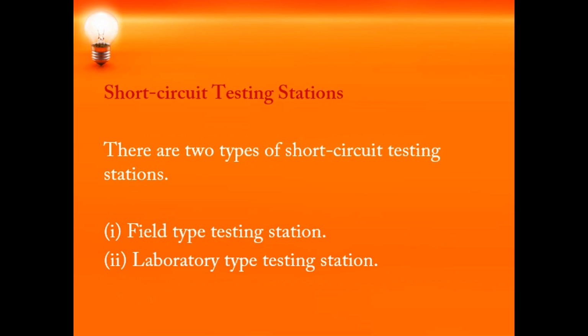So first we will move on to short circuit testing stations. Okay, mainly there are two types of short circuit testing stations. One is in the field, that is under the existing real situations, the present situation, and the other one is the laboratory type, where you have a setup. So short circuit testing will be performed either on the field or on the laboratory type testing station. So we will see what a field type testing station and a laboratory type testing station are in detail. In a field type testing station, the power required for testing is derived from a large power system. That is because we know it is in the field, at the actual substations where you are going to conduct this.